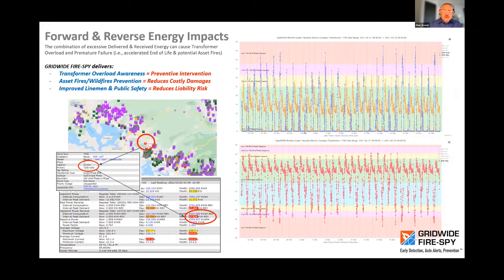If we put this into a graph space, the gold indicators are forward energy overload, just load and overload, and the purple are reverse load and overload. I say overload because this transformer is now experiencing overload on almost a daily basis, and a reverse overload of massive significance, upwards of over 150% of its capacity, on an almost daily basis.